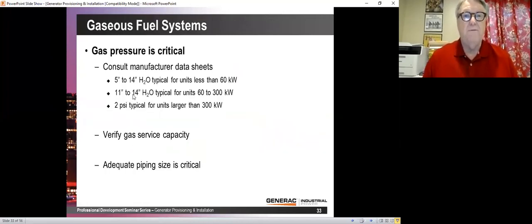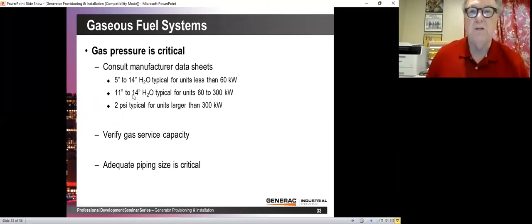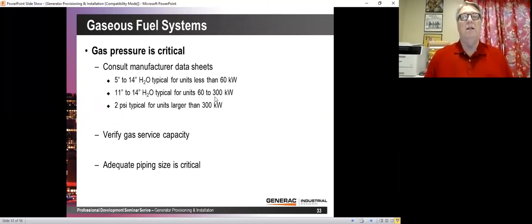Typically, the fuel pressure is 5 to 14 inches for less than 60 kilowatts, 11 to 14 up to 300, and 2 psi typically larger than 300. A little over 27 inches is 1 psi. So you can see we're going from maybe a fifth of a psi to a half of a psi for your smaller generators, and a little less than half of a psi, or around half of a psi, for 300 kilowatts and below.